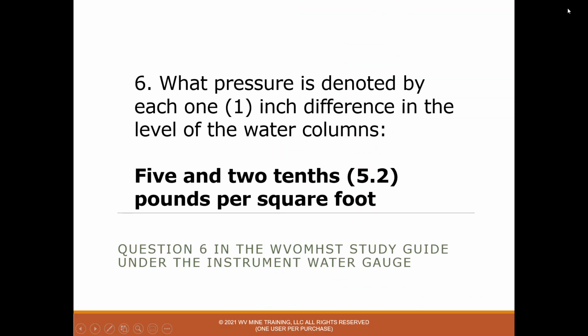Question 6, what pressure is denoted by each inch difference in the level of the water columns? And the answer to that is 5.2 pounds per square foot. So a cubic foot of water weighs 62.4 pounds. So each square foot, if you had a square foot, 12 by 12, and you had 1 inch of water in that, that would equal 5.2 pounds. So 5.2 pounds per square foot.